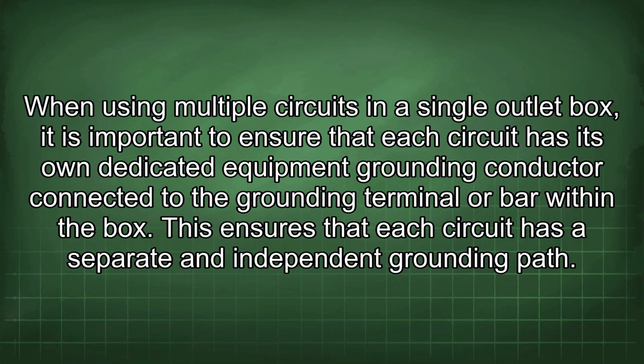When using multiple circuits in a single outlet box, it is important to ensure that each circuit has its own dedicated equipment grounding conductor connected to the grounding terminal or bar within the box. This ensures that each circuit has a separate and independent grounding path.